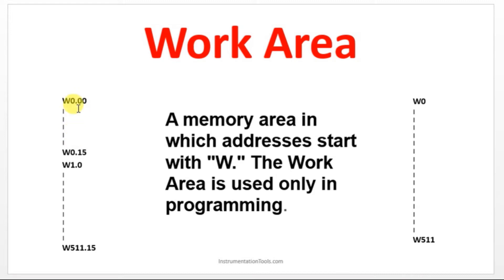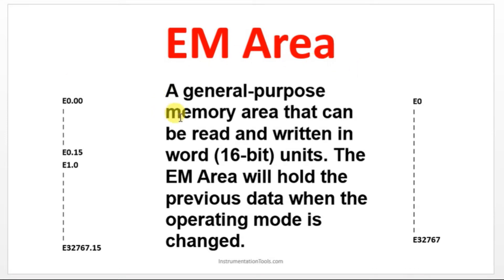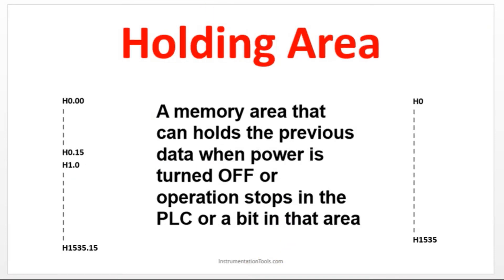You can utilize this 16-bit for the word, and we have the DM area. It's for 16-bit units. Once we start the instruction, you can understand where and when we are going to use these kind of addressing. We have an EM area. This is for a general purpose memory area that can be written and read in 16-bit. You will be using this complete 16-bit for one word. The EM area will hold the previous data when the operating mode is changed.